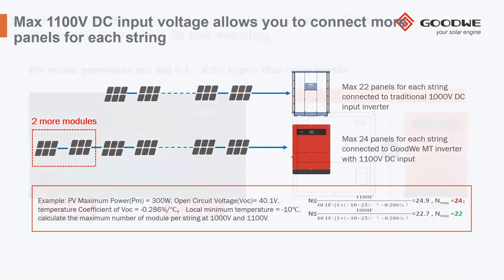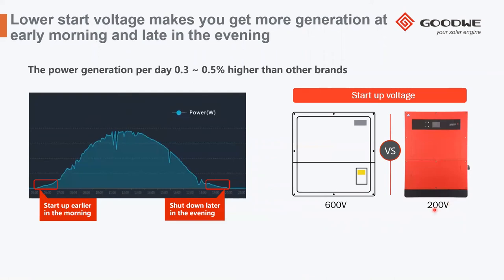Another interesting feature is the very low startup voltage for the MT series. It's 200 volt only. And this means that with a small sunlight, like you have in the early morning or in the evening, even with these small sunlights, the system is capable to work. So you get the advantage of this early and this late light to get additionally 0.3 up to 0.5 higher energy than other brands, which, as an example, can have a startup voltage at 600 volt.